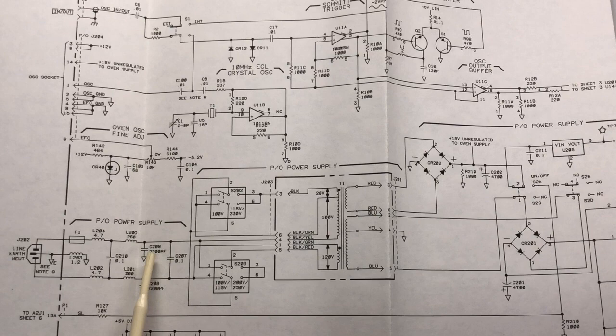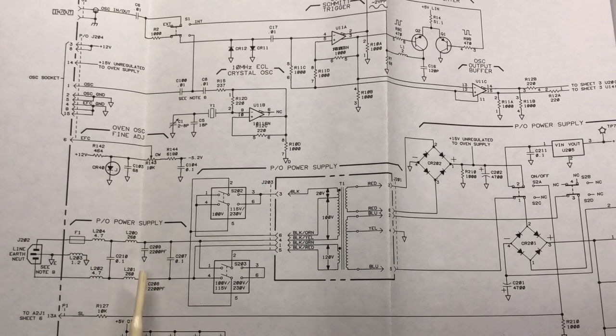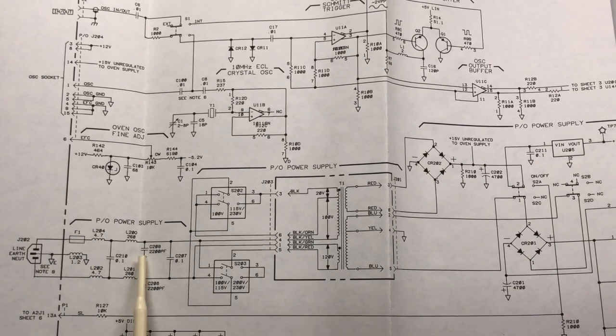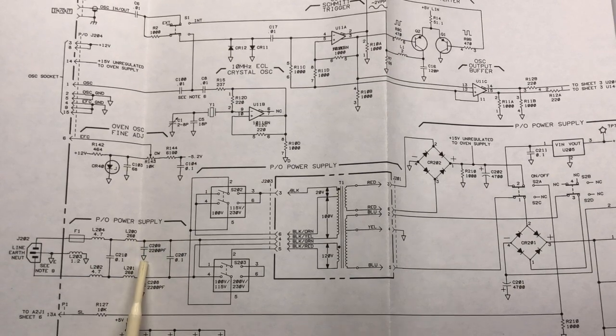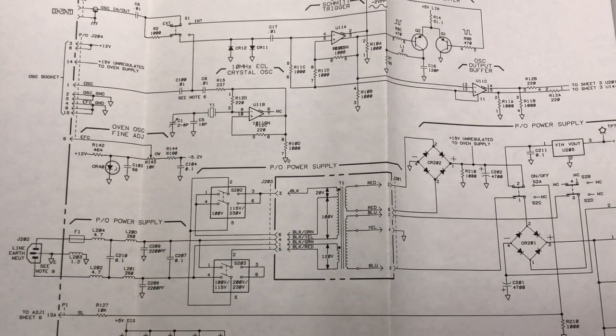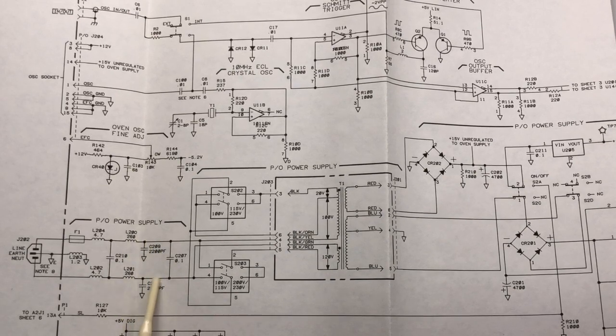Now, right here we have C209 and C208, the 2200 picofarad capacitors. And you can see there's that triangle symbol again, all right? So when you see that triangle symbol here and here and here, those are the chassis ground connections, all right? So those are all considered the same point, that's the chassis, a common ground connection in the instrument. Now you can see that one of these capacitors is from the hot AC line to the chassis, and this is from neutral to the chassis. Again, when you have a capacitor that's connected on the AC line, whether it's the hot side or the neutral side, it needs to be a safety rated capacitor, and these must be the Y class capacitors, very often Y1 or Y2 class capacitors.